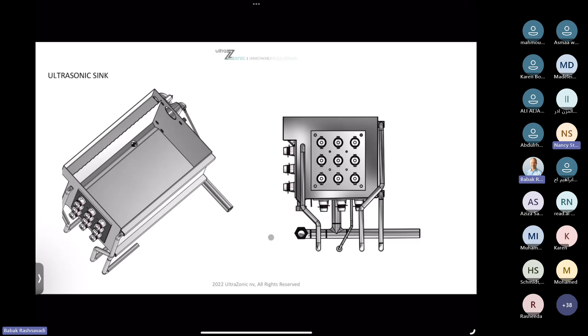There you can see the picture in more detail. The bottom has transducers, the short side has transducers, and the long side has transducers. So we are really creating a kind of 3-dimensional cleaning. It's a triple-sided irradiation, which creates a very efficient cleaning efficacy in a short time. And what I wanted to add: in every corner, or even in the middle of the field, or on the bottom, you will find everywhere the same cavitation fields. This is really an innovation that we never could have believed could help the CSSD in hospitals.